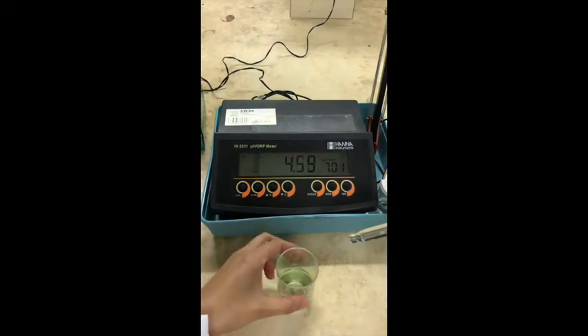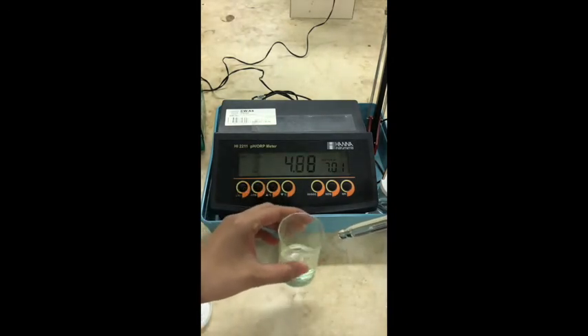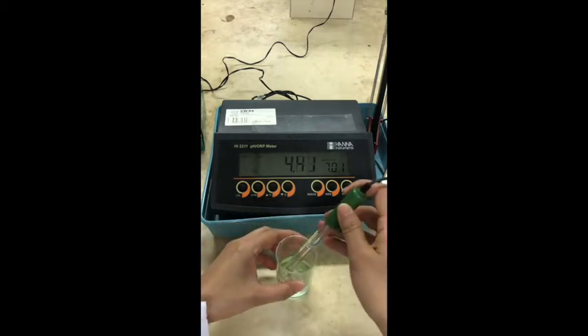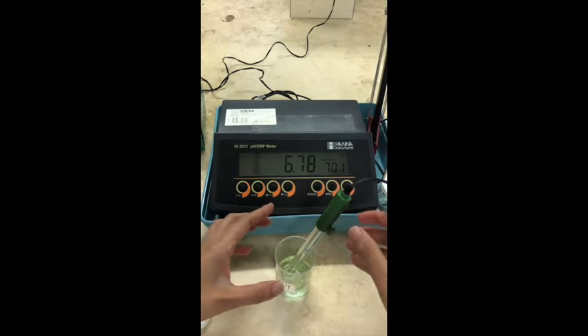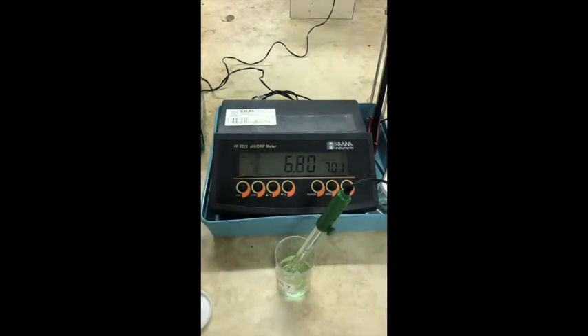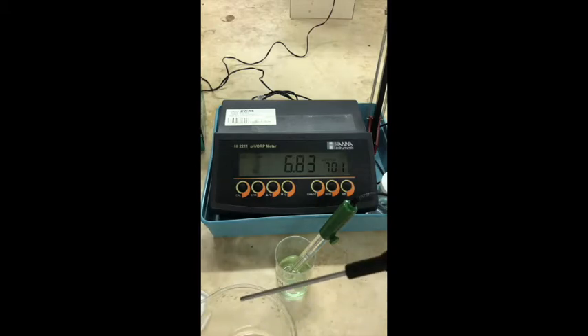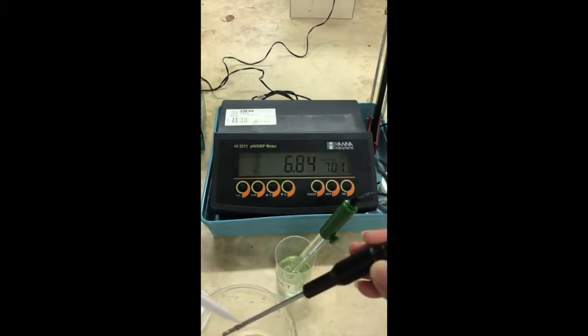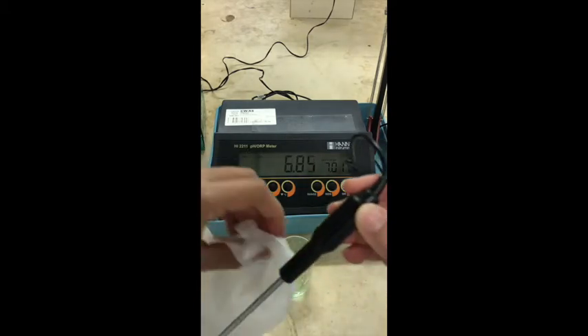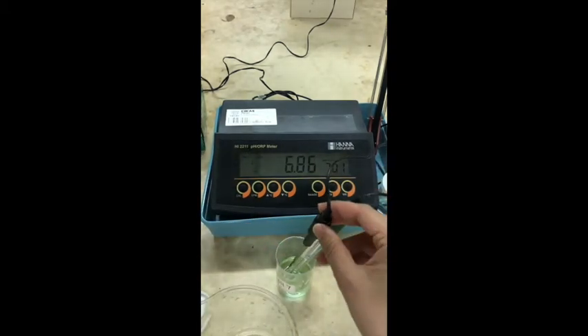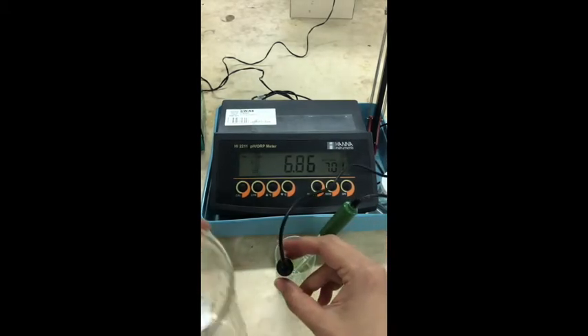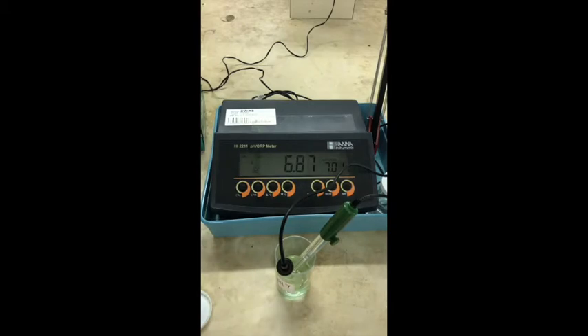Stir the buffer solution before placing the electrode to homogenize the mixture. Use the glass probe as a stirrer. And then add the thermocouple into the buffer solution. Before that, we need to rinse the thermocouple with deionized water and wipe it with the lens paper. Put the thermocouple inside the buffer solution. The instrument will measure the potential continuously until it gets steady.